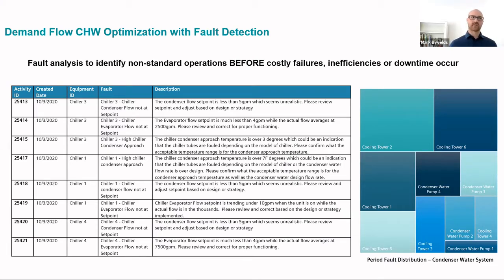Have a system in place that collects all that data, and rather than relying on a person complaining there's an issue, or facilities management looking for a problem, which in reality they often don't have time to actively seek out, we let the system tell us where the problem is, what the likely problem is, and a solution as well. An example here is just taking data that would already exist in most buildings.